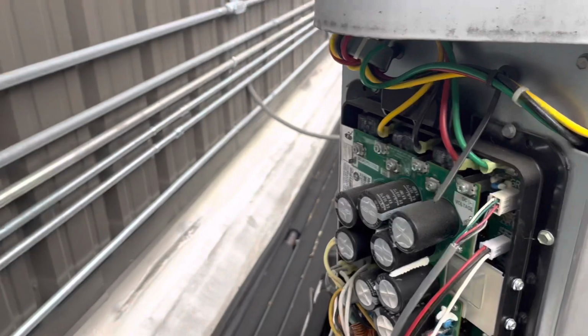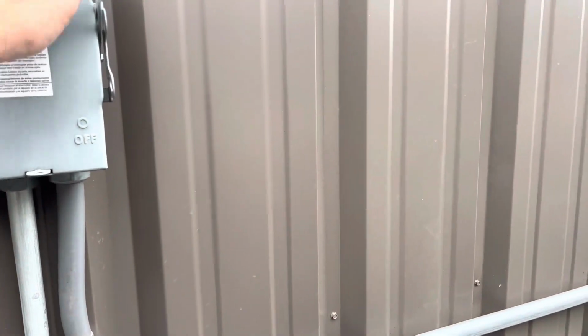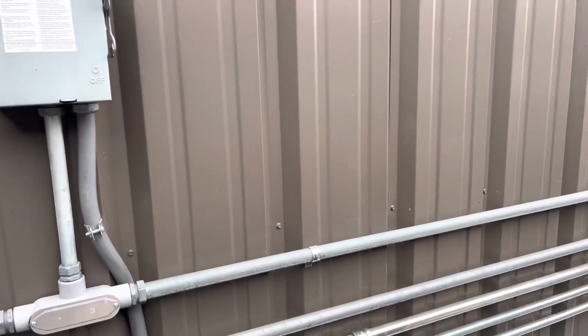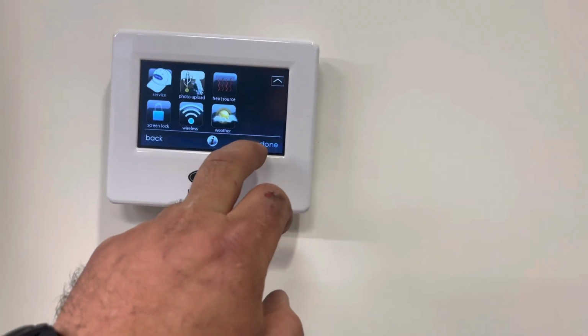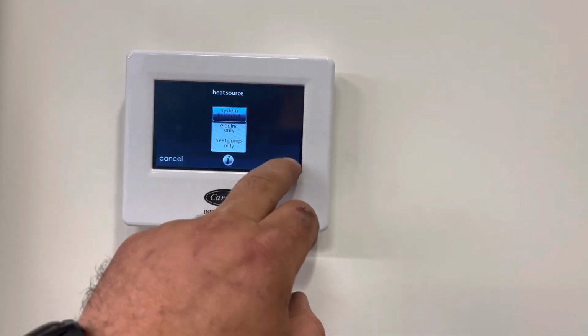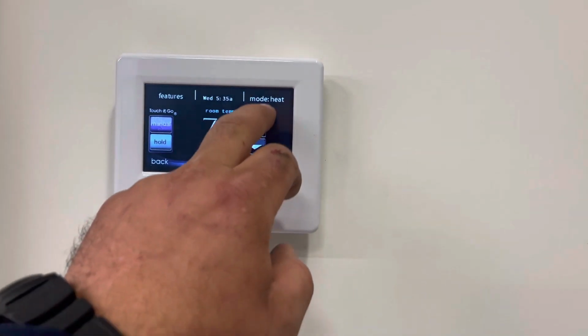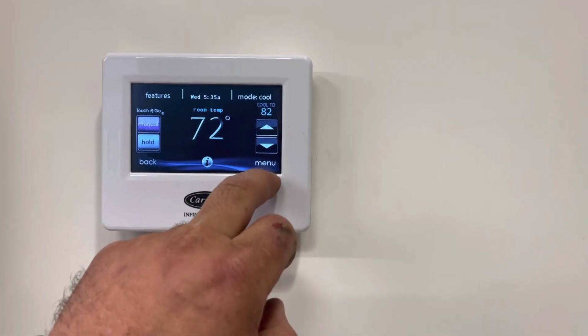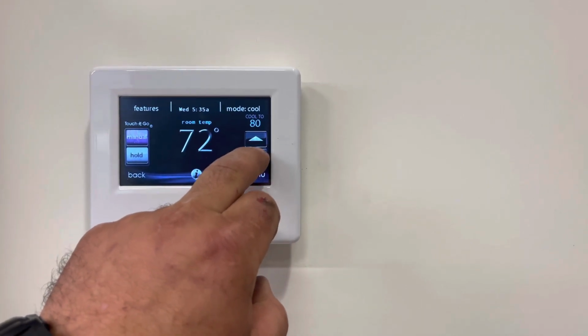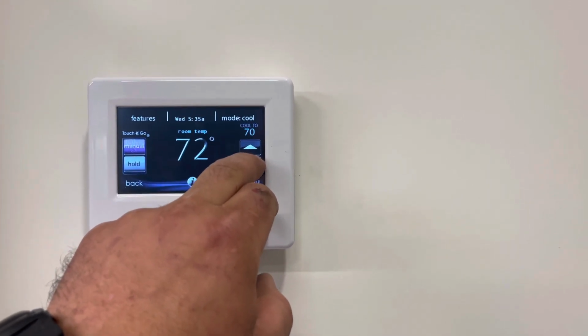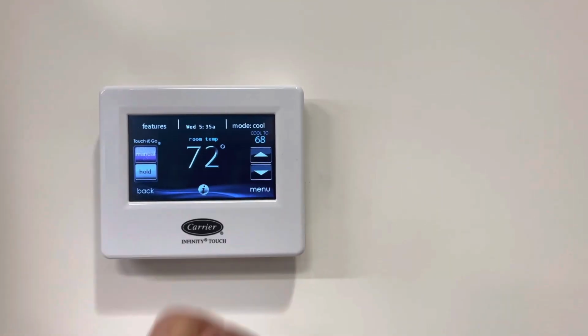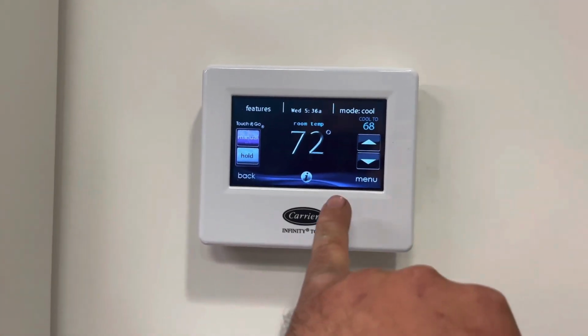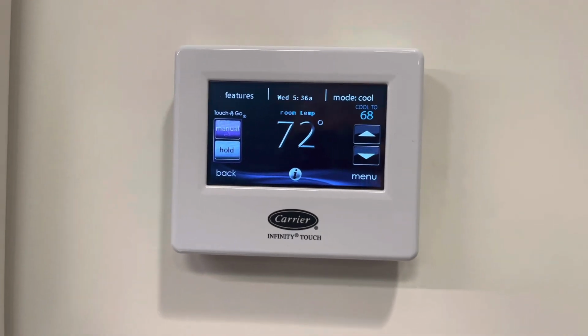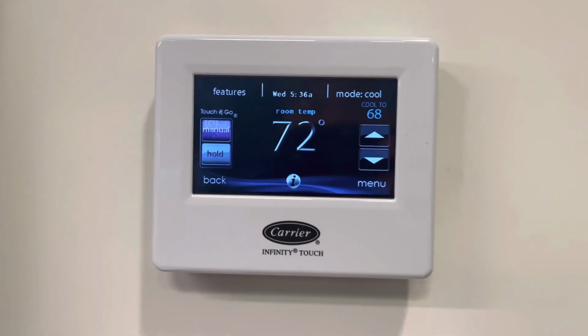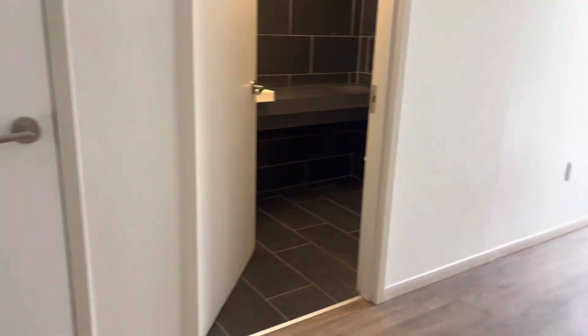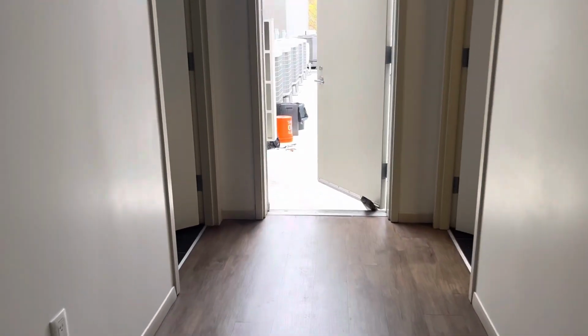But let me go downstairs after I power this up, put it back to heating, and see if I get an error code. Because right now it's on heat source only, so we're going to put system in control. Done. I'm going to switch over for a call to cool. And we're going to call for 68. I'm going to wait 5 minutes. 7 minutes. Different code than I was getting before, which was inverter compressor error. That'll tell me the logic's actually doing its thing. I'm going to wait the 5 or 7 minutes up here. It's kind of stuffy down there with all the people working.